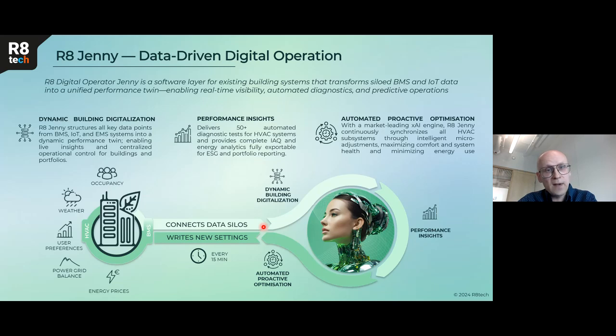After the connection is made, we are collecting data, we're analyzing, and we are doing fault detection. Fault detection is a little bit different than what the BMS is doing. BMS is usually doing more alarm-based fault detection, but we are doing data-based fault detection. Performance insights: during the control, we are checking and analyzing consumption data, and we are preparing different reports, usually monthly reports, annual reports, and so on. And during the control, we are doing 24/7 optimization, and if necessary, we are overwriting the setting values in BMS. It means we are using the same setting values that regular maintenance is using, so different set points, etc.